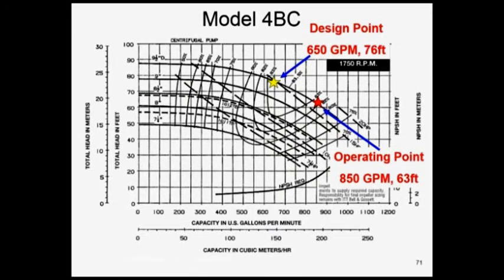850 GPM. So you're flowing 850. The only requirement was 650, and that's why it's noisy. You've got high velocity going on. You've got a noisy system because you're overflowing. How would you balance this system?